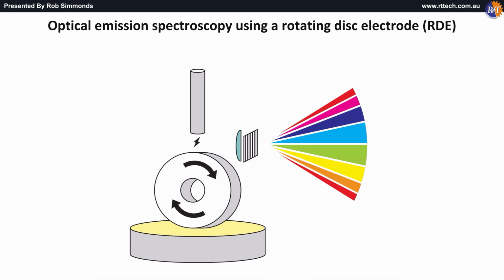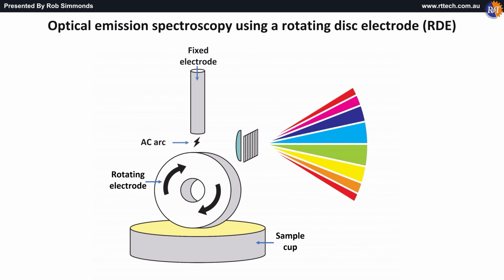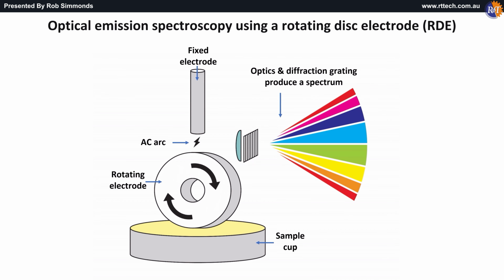Optical emission spectroscopy using a rotating disc electrode. This is a more manual system, with the electrodes loaded into the machine individually. The electrode rotates in the sample cup with the oil. The electrode has been soaked in the oil beforehand for a predetermined time. The electrode supplies the arc to give the plasma. The optics and the diffraction produce the spectrum, and the analysis results are recorded.